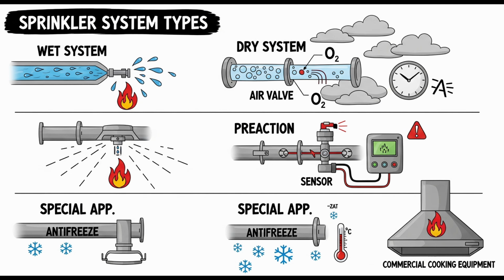And now, perhaps the single most critical safety feature required in this whole cooking protection section. Absolutely. It's the mandatory automatic fuel and heat shutoff. This is a non-negotiable requirement. The operation of any cooking equipment sprinkler or automatic spray nozzle, whether for equipment, hood, or duct protection, must automatically shut off all sources of fuel and heat to all the cooking equipment that requires protection under that specific ventilation system.